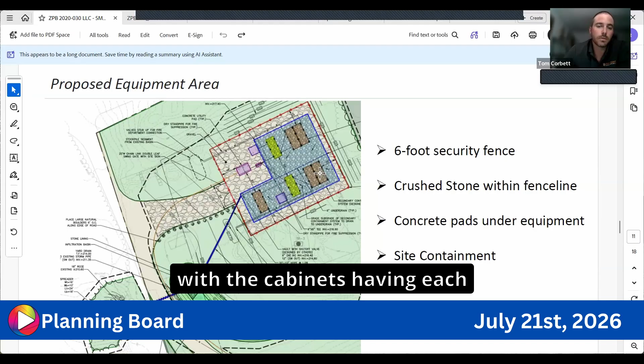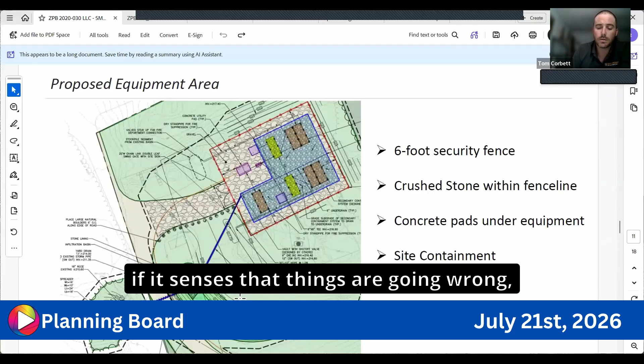We have multiple redundancies here, with the cabinets having each secondary containment system, as well as the site itself. The containment system is designed to evacuate stormwater through the normally open valve in the corner here. There's a vault in this corner that collects all the water through under drains within this containment system. When the system senses an emergency, that valve will close automatically. There are also two manual valves outside of the fence, one before the water quality unit and one after.